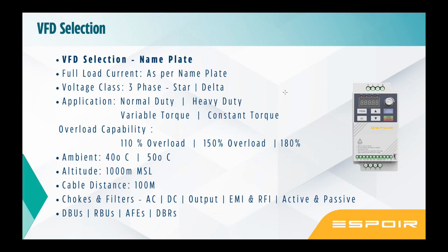Anything other than a standard fan and pump is a constant torque or heavy duty application. From a design point of view, how variable torque and constant torque drives are designed is purely based on the overload capability. Fans and pumps don't need overload capability as much as heavy duty applications. In a variable torque or normal duty application, the design standard is generally to deliver 110% of the overload current as per the frame size of the drive. In a constant torque heavy duty application, it is generally capable of delivering 150% of overload current for 1 minute, 180% for 3 seconds, and 200% for any instantaneous requirement of torque.